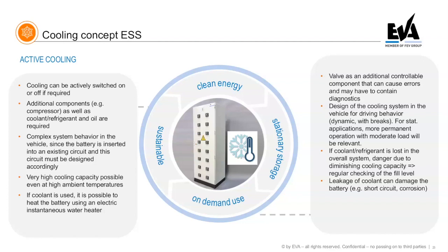Another important thing, not only for the design phase but also the service phase, is that any leakage of the coolant can cause battery damage, for example short circuit or corrosion. This is something you have to take care of whether you use passive or active cooling.